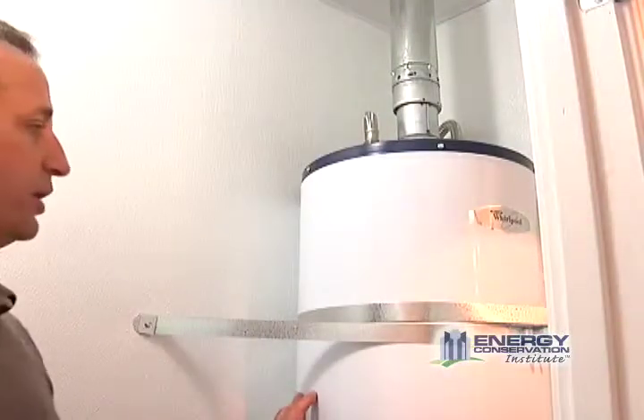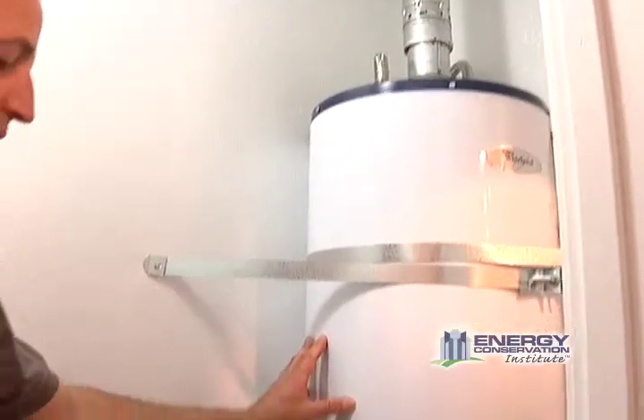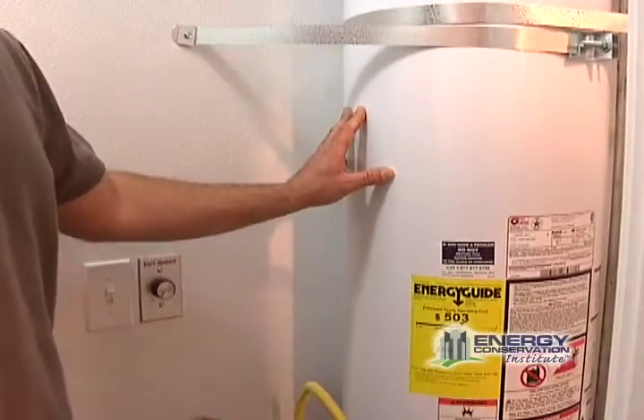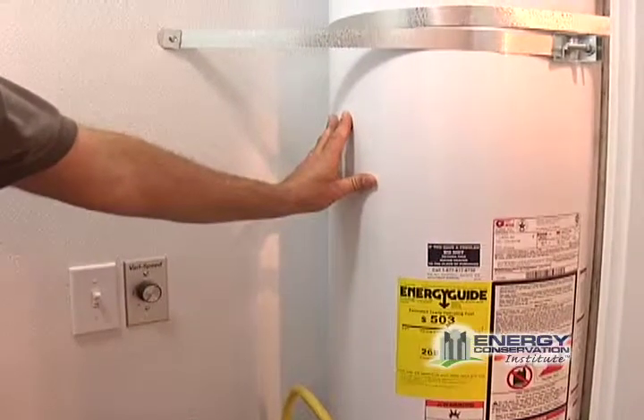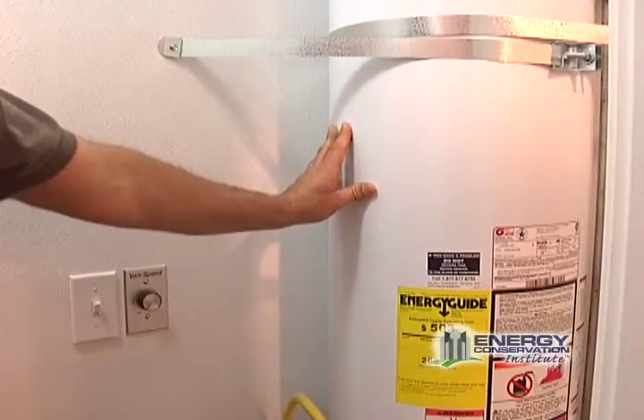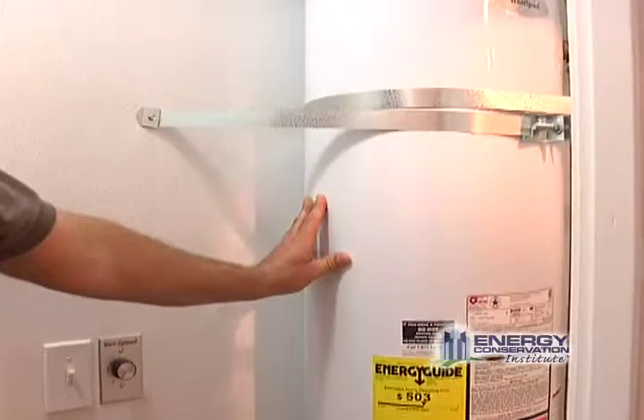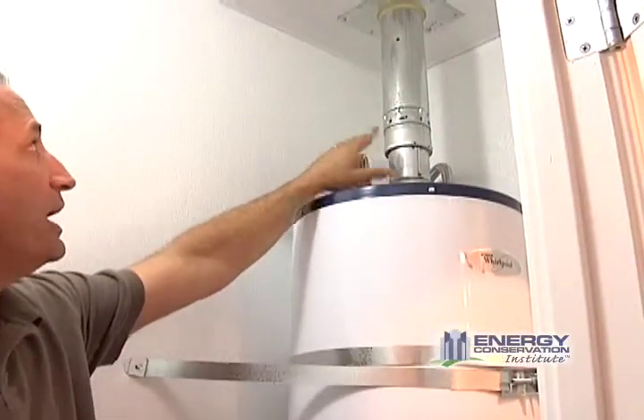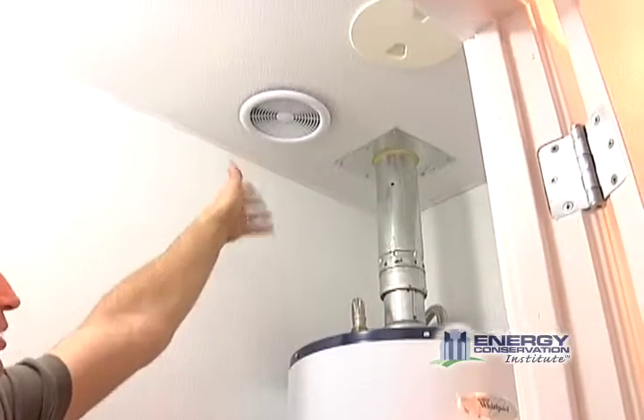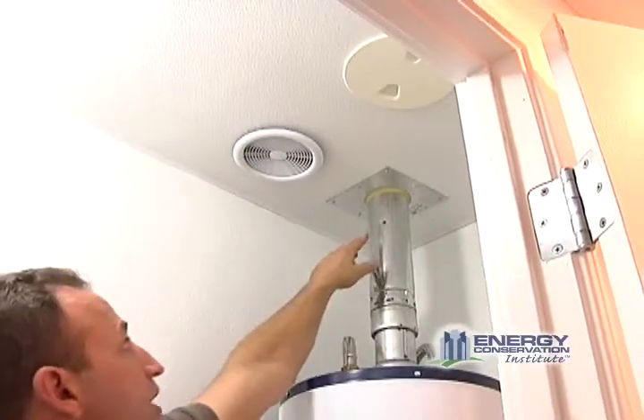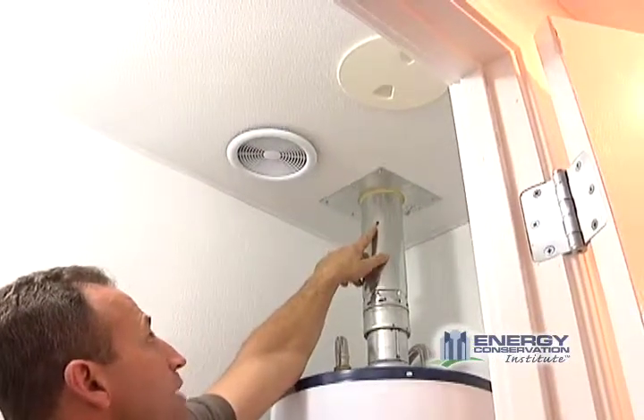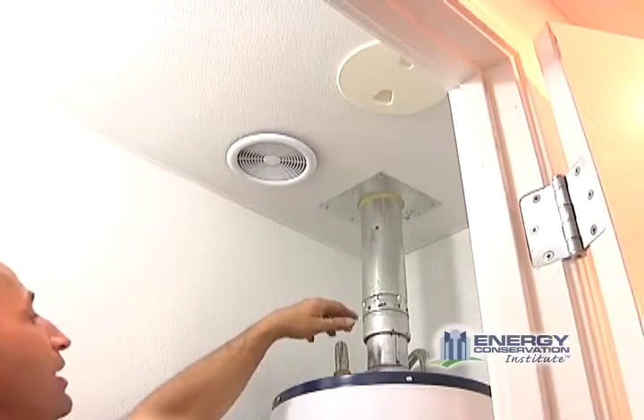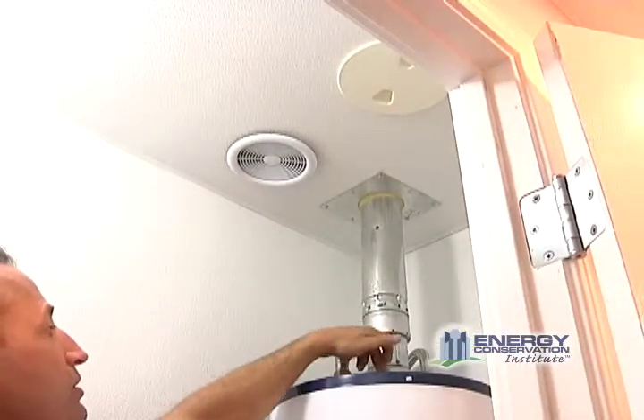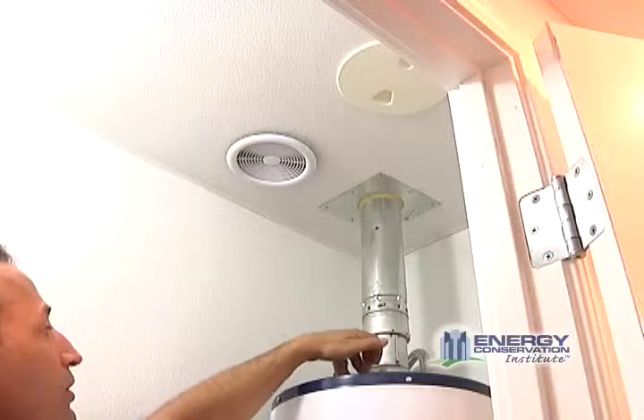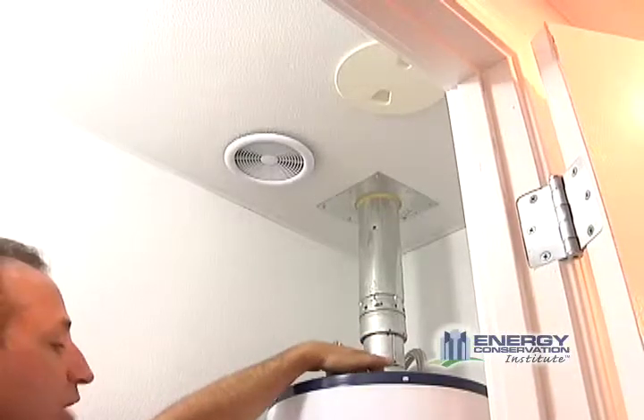So on this side of the laundry room, we have a traditional gas-fired water heater. This again runs on propane like all of our other appliances in here. And this is a traditional water heater that you'd find in the average residential home. We're using a 3-inch B vent here, which passes through the attic space and then out through the roof line. You'll see we've got a hole already drilled in the flue pipe here for you to do draft testing. And if you like, you can drill holes here in your diverter to measure CO down in the throat.